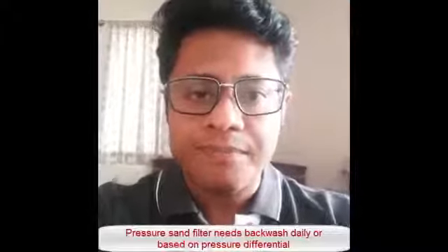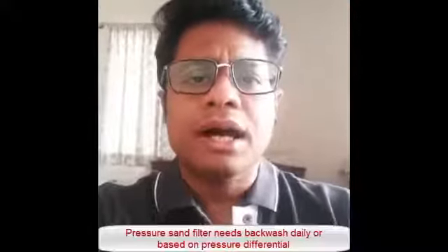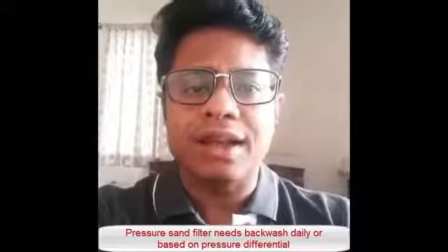What should you do? First, backwash is required for the sand filter. Backwash is generally designed for a daily cycle, a daily backwash of 15 to 20 minutes. For the activated carbon filter and sand filter, it is a similar kind of backwash, based on the accumulation of dirt. Generally, backwash is done based on pressure differential. You will have a pressure gauge in your system which will indicate a higher pressure if the cylinder chokes more. Based on the pressure differential, backwash needs to be done, but generally it is a daily backwash for sand and carbon.